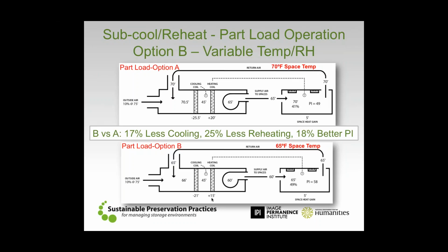which means now if I start comparing and looking at the overall energy picture in the preservation picture of this particular scenario, we had one option up at the top, that part load option A, where on a 75-degree day, we were doing the same amount of preservation, but we were using more energy, right? If we use this part load option B and we change that space condition, we allow ourselves to be flexible in terms of temp and the relative humidity that's being held, but maintain that same dew point condition, notice that now I can get an 18% better preservation quality, right? A slower rate of chemical decay for 17% less energy at the cooling coil and 25% less energy at the reheat coil. Win-win, win, all the way across the board.